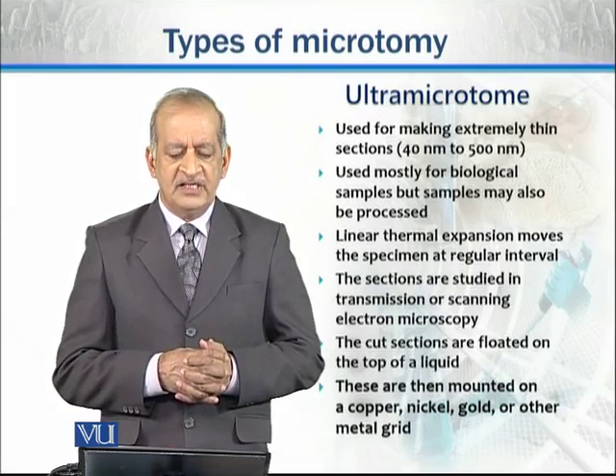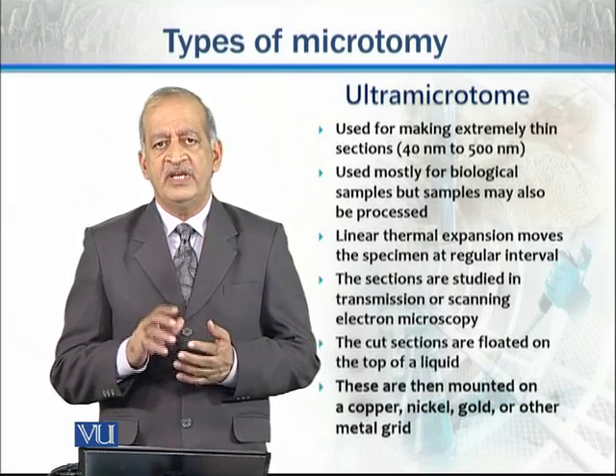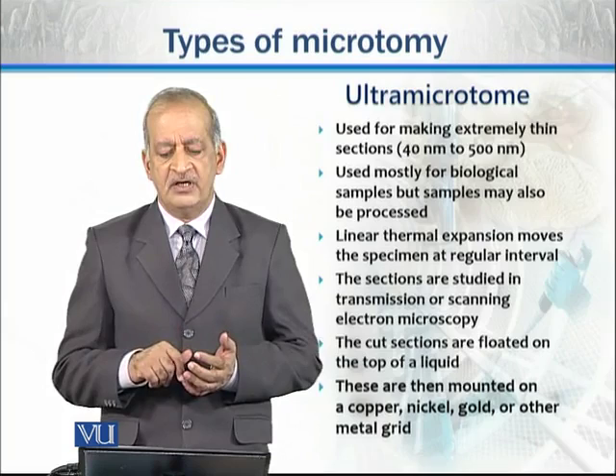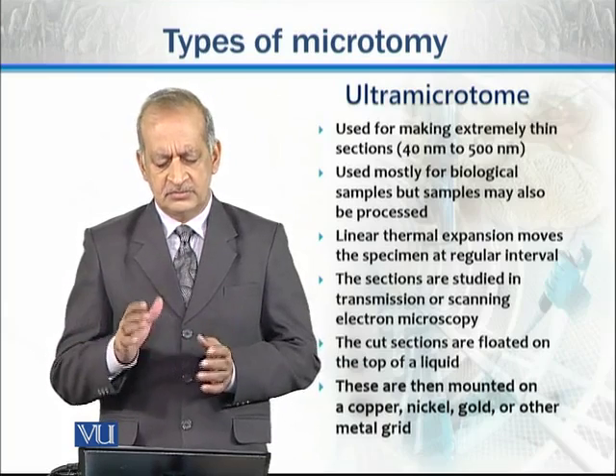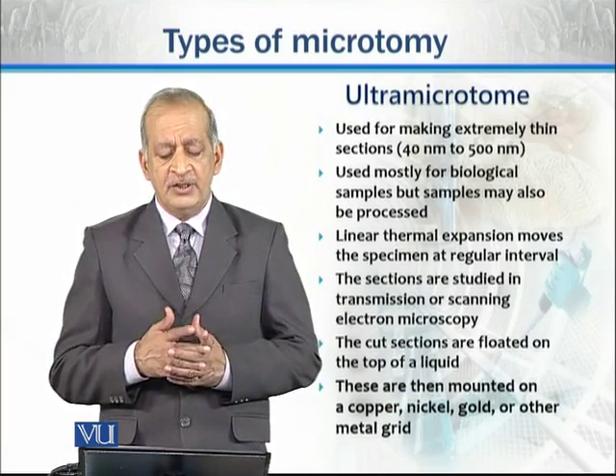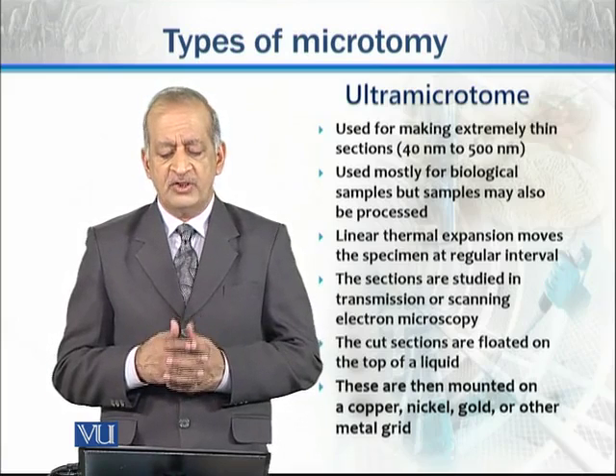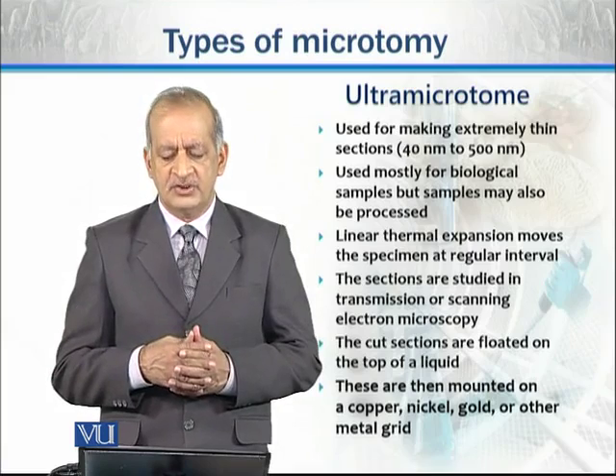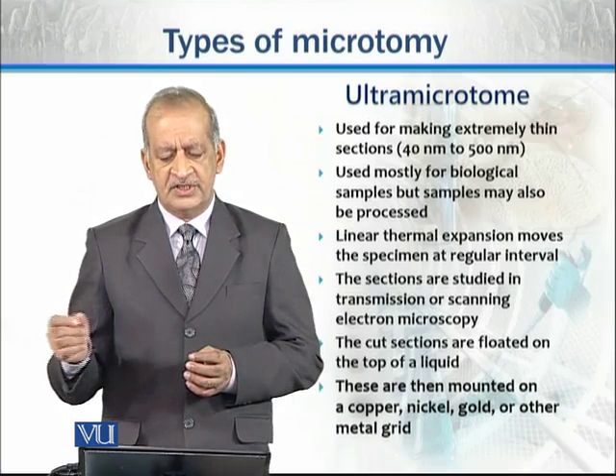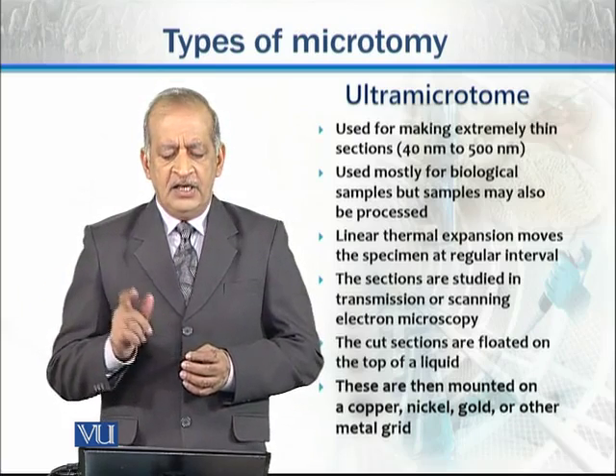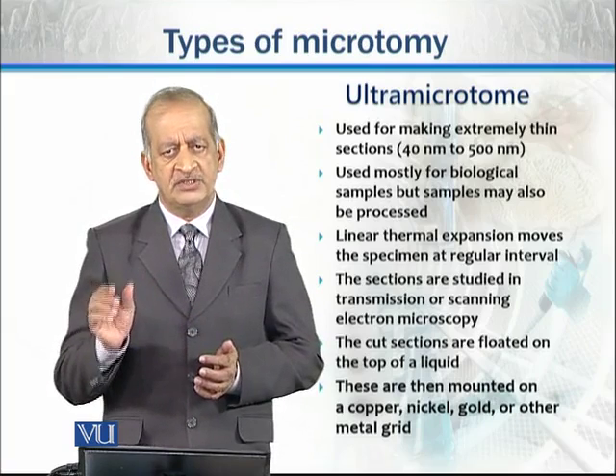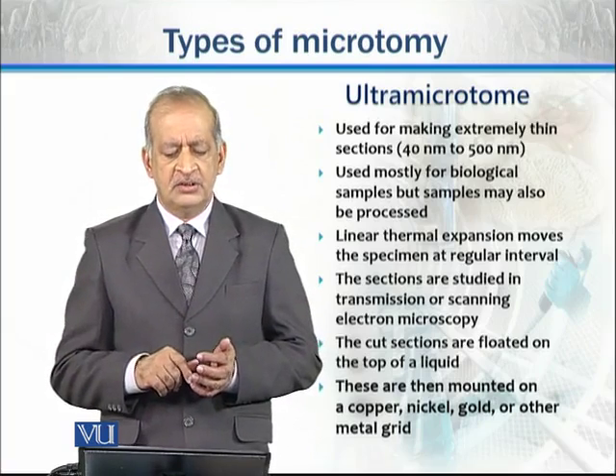The ultramicrotome, as the name indicates, is used for making very thin sections, with thickness ranging from 40 nanometers to 500 nanometers, varying according to the type of study. This technique is mostly used for biological samples but can also be applied to non-biological samples such as plastics. Linear thermal expansion moves the specimen at regular intervals according to the set thickness.